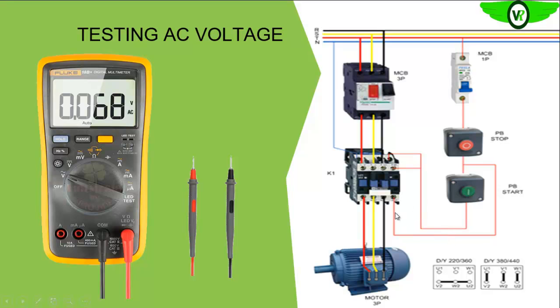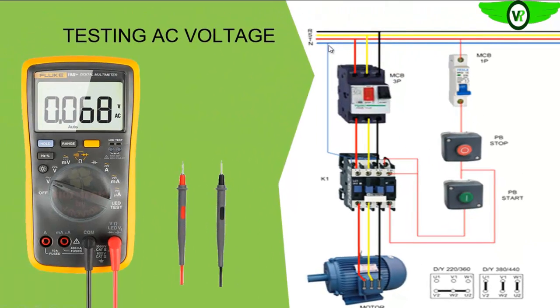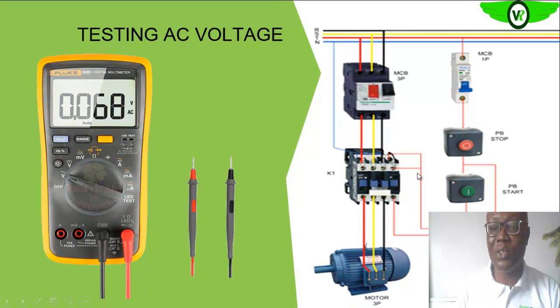So now you will see that the output from this control circuit is feeding the contactor coil. Look at this end of the contactor coil. One end of the neutral from your power supply is to one end of the contactor coil, while the output from your control is to the other end of the contactor coil. So when this is closed, power will be sent to your contactor coil, and it's expected that the coil will be energized, and that will close the contactor, and that of course will close power to your electric motor. So if the circuit is functioning normally like that, that clearly tells you that the problem is not with your circuitry, both control and the power circuit. So you can now go to your electric motor for further tests. So we'll see later in this program how you can carry out tests on electric motors.